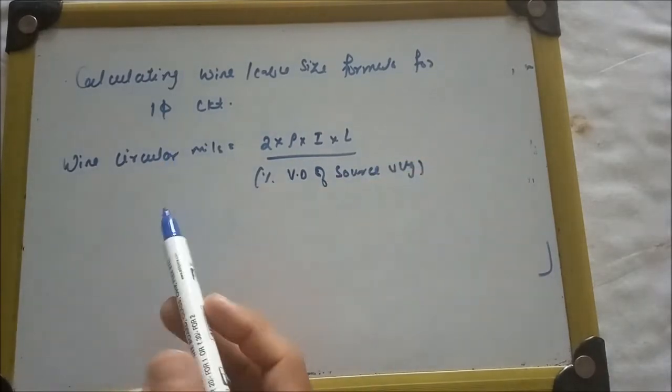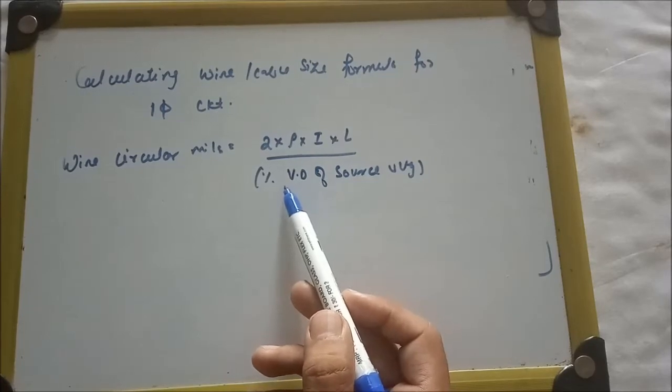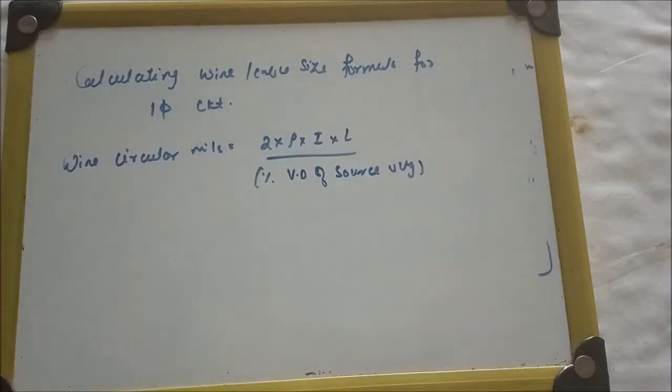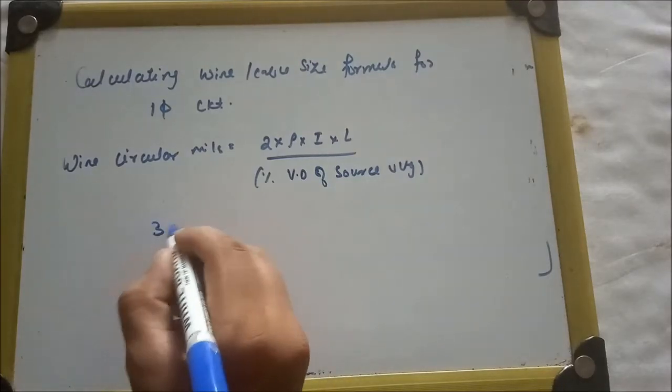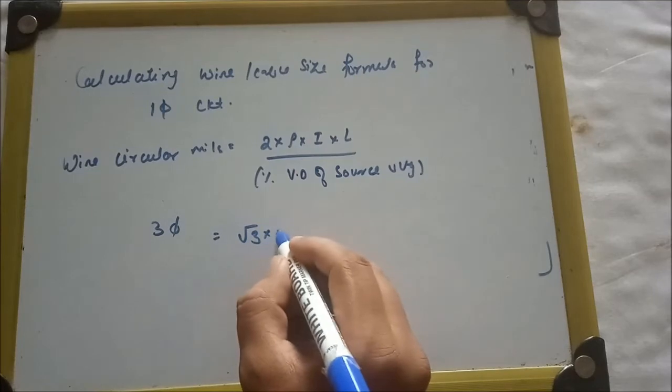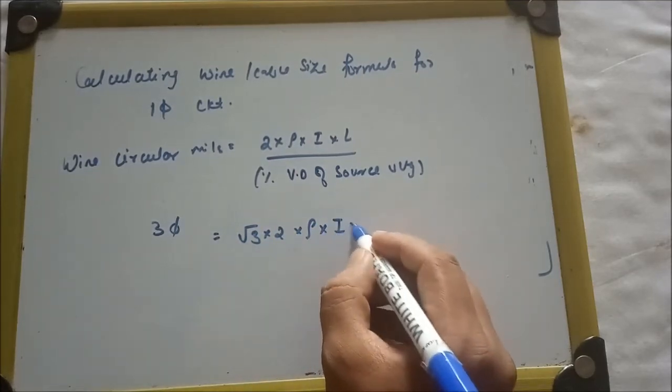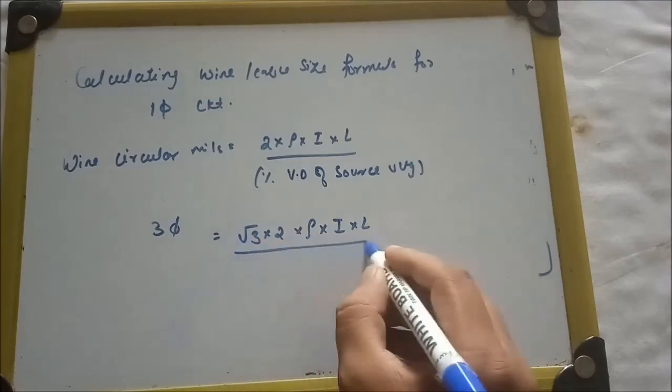For single-phase circuits, it is given as 2 × ρ × I × L divided by percentage allowable voltage drop of source voltage. For three-phase, it is given as √3 × 2 × ρ × I × L divided by percentage allowable voltage drop of source voltage.